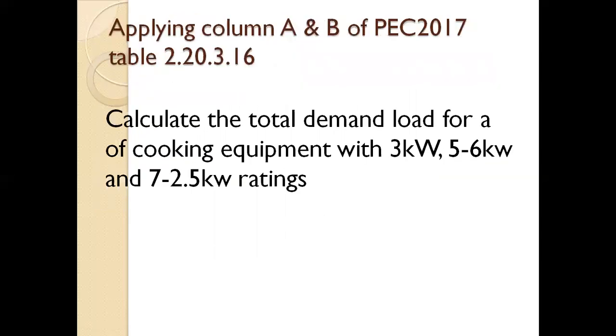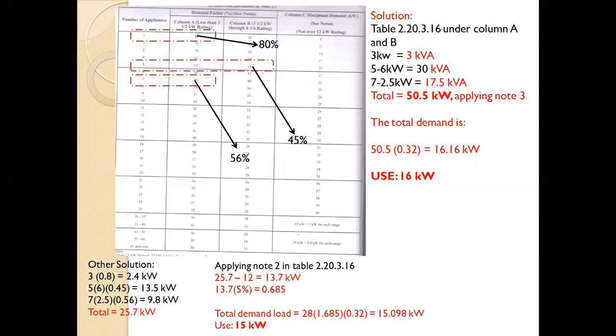Next, we apply columns A and B of PEC 2017, still in Table 2.20.3.16. Calculate the total demand load for cooking equipment with 3 kilowatt, 6 kilowatt, and 7.5 kilowatt ratings. How is that sized? This is the solution. Table 2.20, under columns A and B: for 3 kilowatt, the total is 3 kVA. For the 5, the total demand is 30 kVA, and the 7.5 is 17.5. So the total is 50.5 kilowatt.